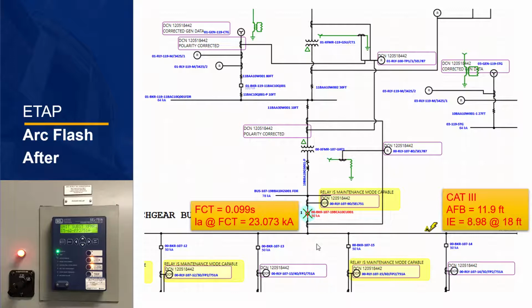This slide shows the same portion of the single line with maintenance mode enabled. As we can see, there is a drastic reduction in the length of time a fault is on the system and the energy reduction gained from it. On low voltage systems, 480 volts and less, we were able to achieve lower than 8 calories per centimeter squared, which is defined as daily wear energies, meaning operators can minimize PPE requirements, making their jobs safer, easier, and more comfortable.